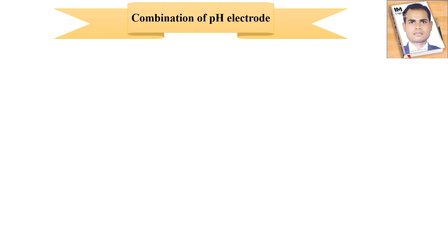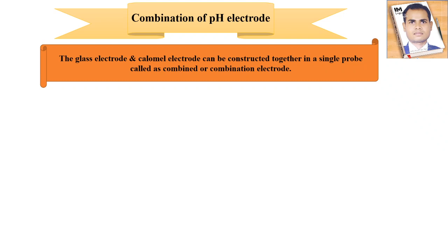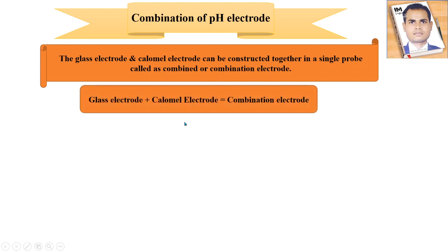Next topic is the combination pH electrode for measurement of pH or hydrogen ion concentration. For the pH instrument, we can connect a combination pH electrode. This is the glass electrode and calomel electrode — both can be constructed together in a single unit. Both electrodes are present at one place, and we call them a combination pH electrode, also known as the combined electrode. So: glass electrode plus calomel electrode equals a combination electrode or combined electrode.